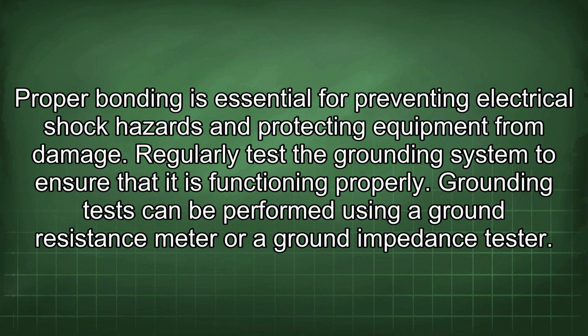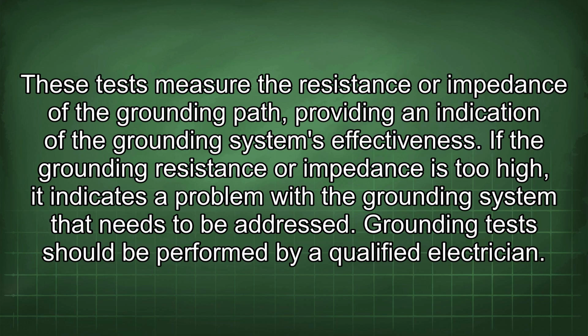Regularly test the grounding system to ensure that it is functioning properly. Grounding tests can be performed using a ground resistance meter or a ground impedance tester. These tests measure the resistance or impedance of the grounding path, providing an indication of the grounding system's effectiveness. If the grounding resistance or impedance is too high, it indicates a problem with the grounding system that needs to be addressed. Grounding tests should be performed by a qualified electrician.